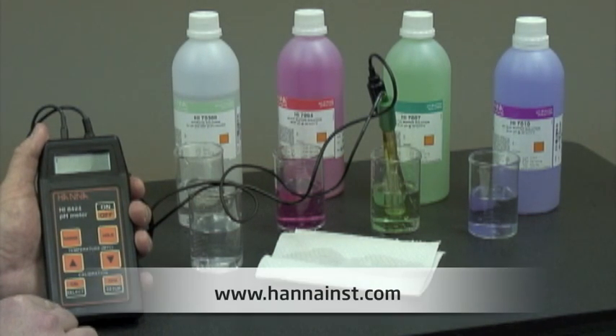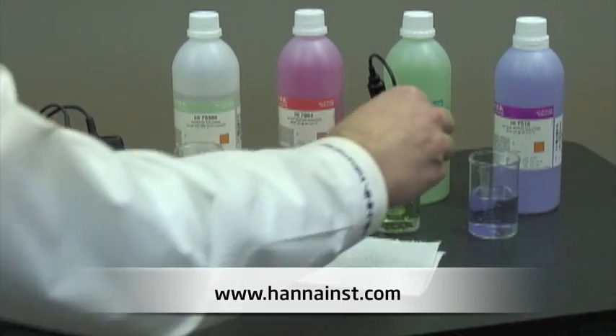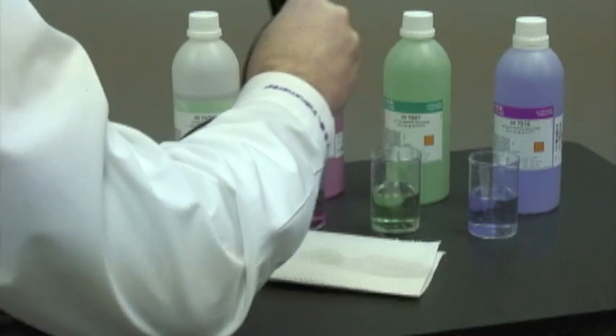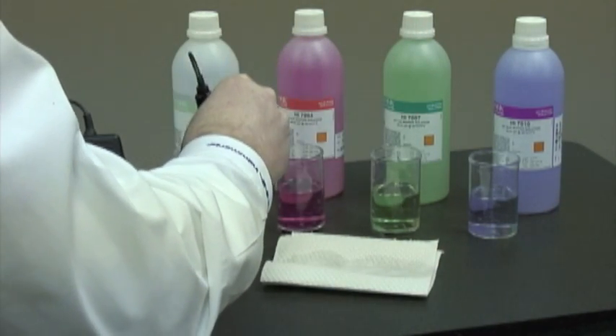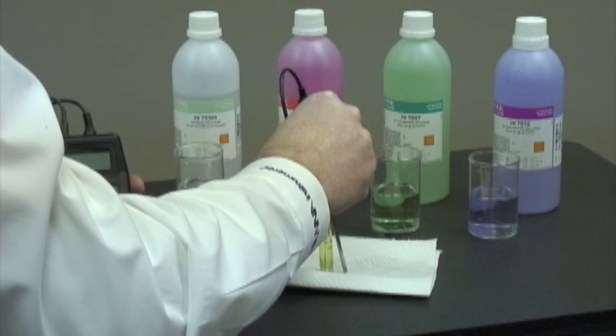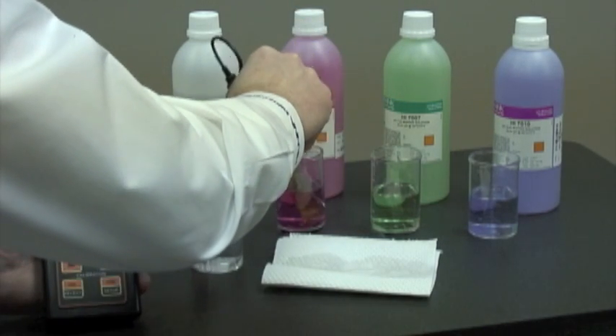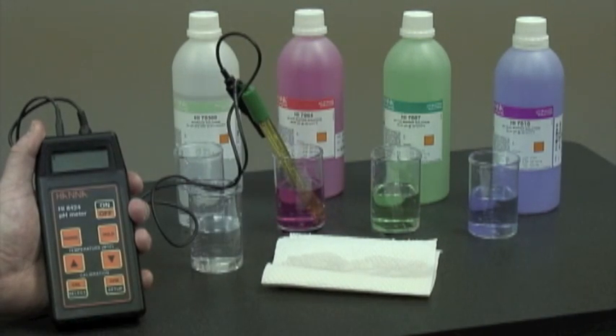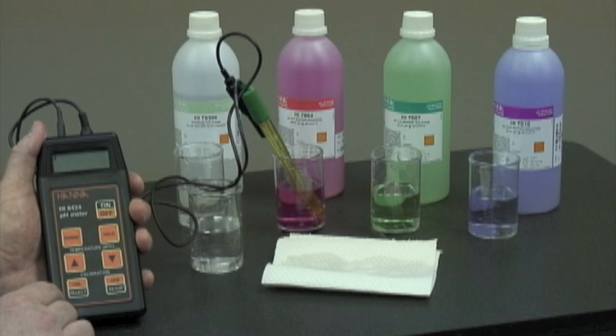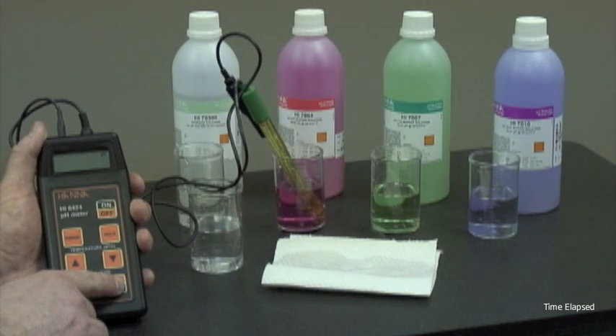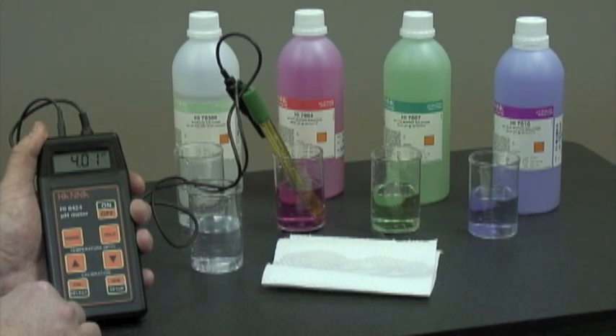Now it's prompting us for pH 4. You can use either pH 4 or 10 if you want to do a pH 2-point calibration. In this case, we're going to measure an acid, so we'll use pH 4. Now we just need to wait for the confirmation and press the button. Now we're ready to measure.